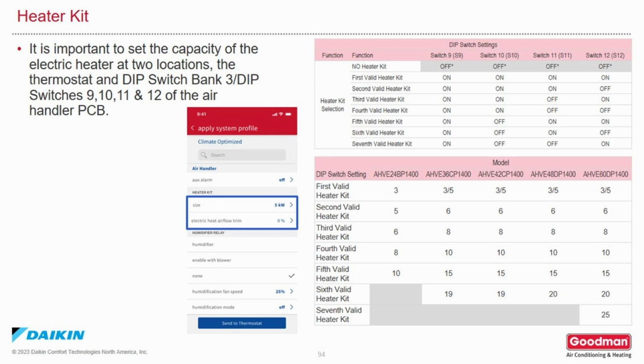When using a heater kit, it is important to set the capacity of the electric heater at 2 locations: the thermostat and the dip switch bank number 3, dip switch settings 9, 10, 11, and 12 of the air handler circuit board. Set the dip switches according to the chart on the right side of this screen, also found in your IOM.